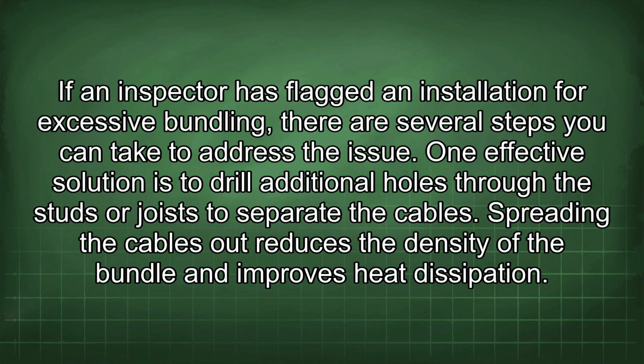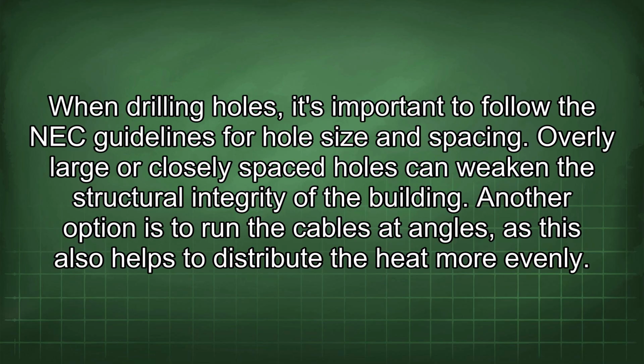If an inspector has flagged an installation for excessive bundling, there are several steps you can take to address the issue. One effective solution is to drill additional holes through the studs or joists to separate the cables. Spreading the cables out reduces the density of the bundle and improves heat dissipation. When drilling holes, it's important to follow the NEC guidelines for hole size and spacing. Overly large or closely spaced holes can weaken the structural integrity of the building.